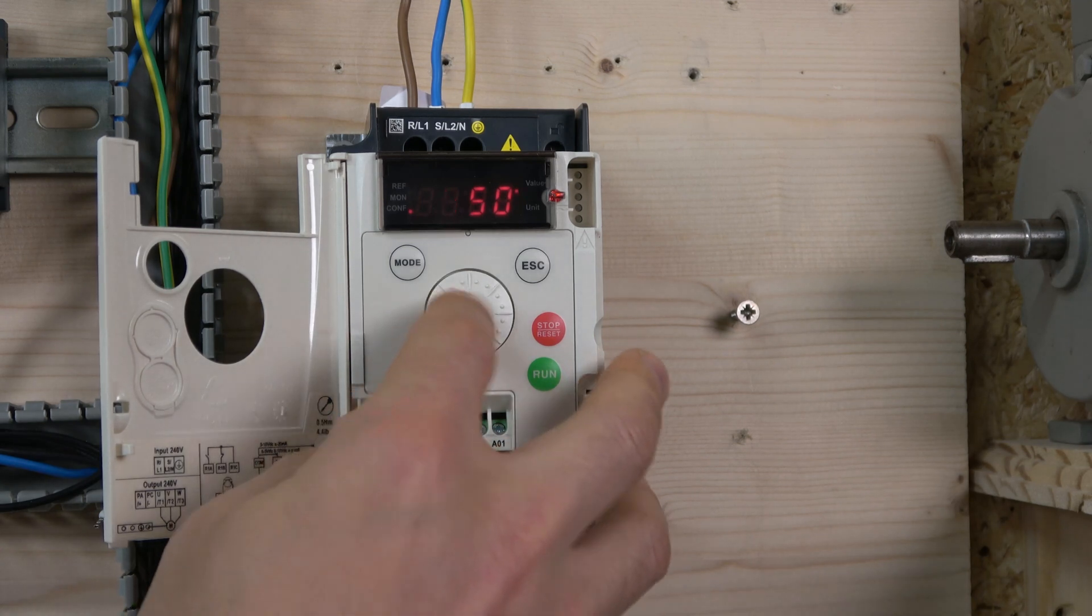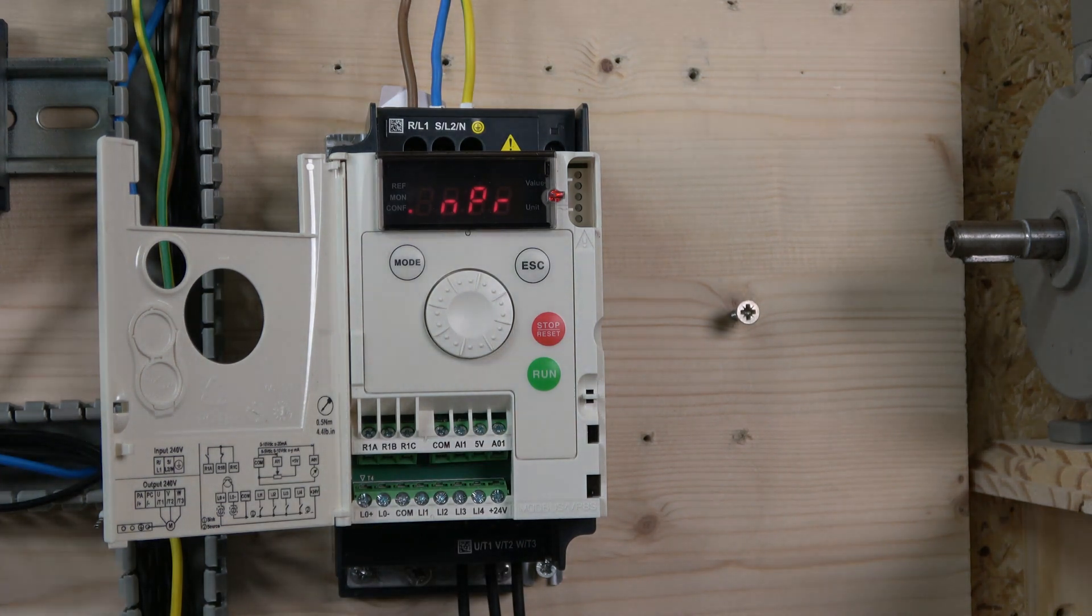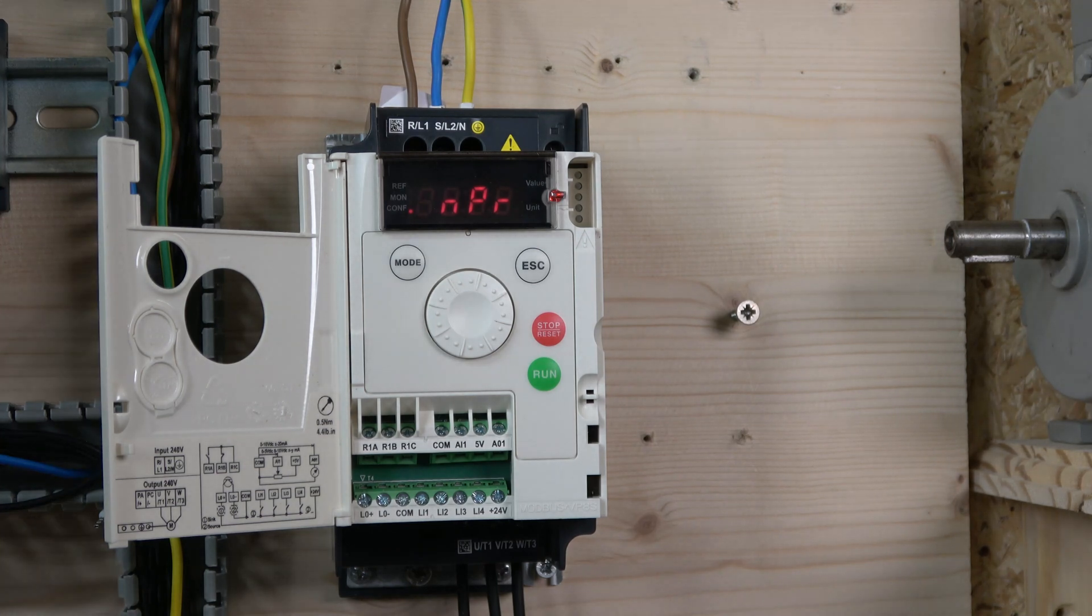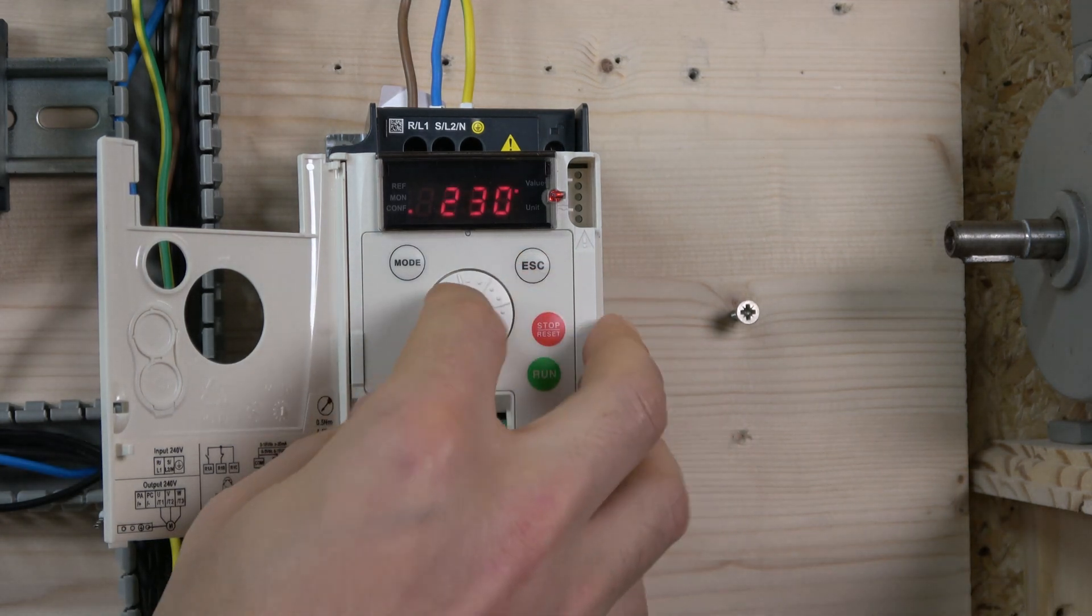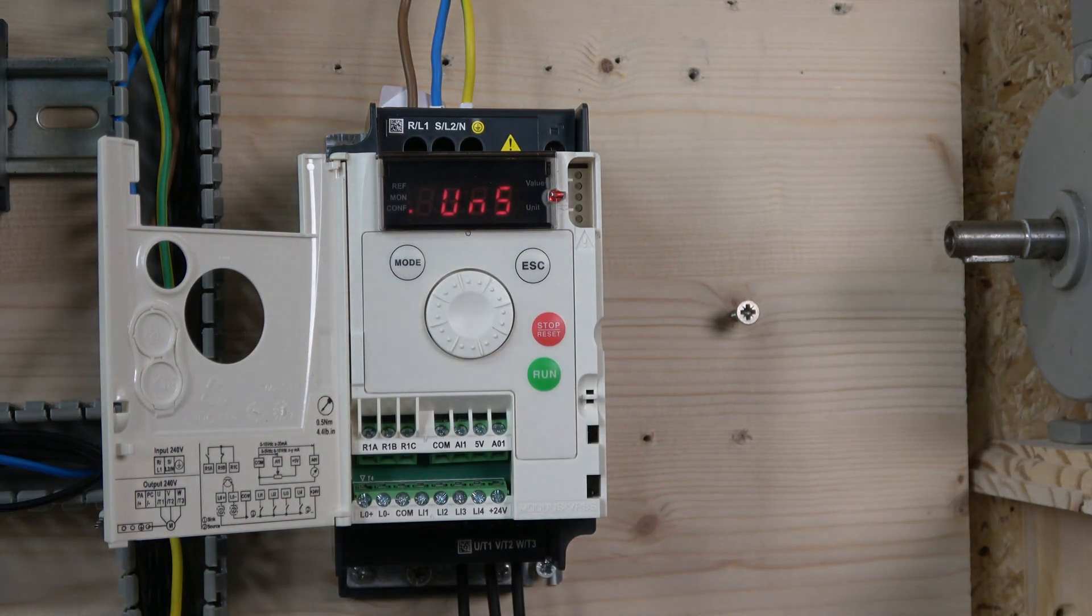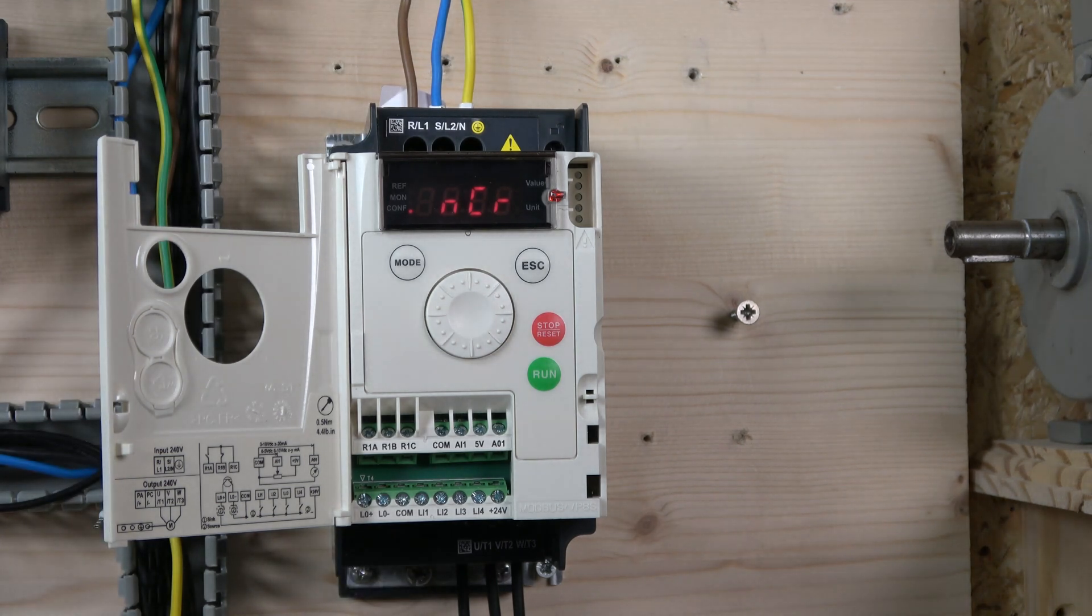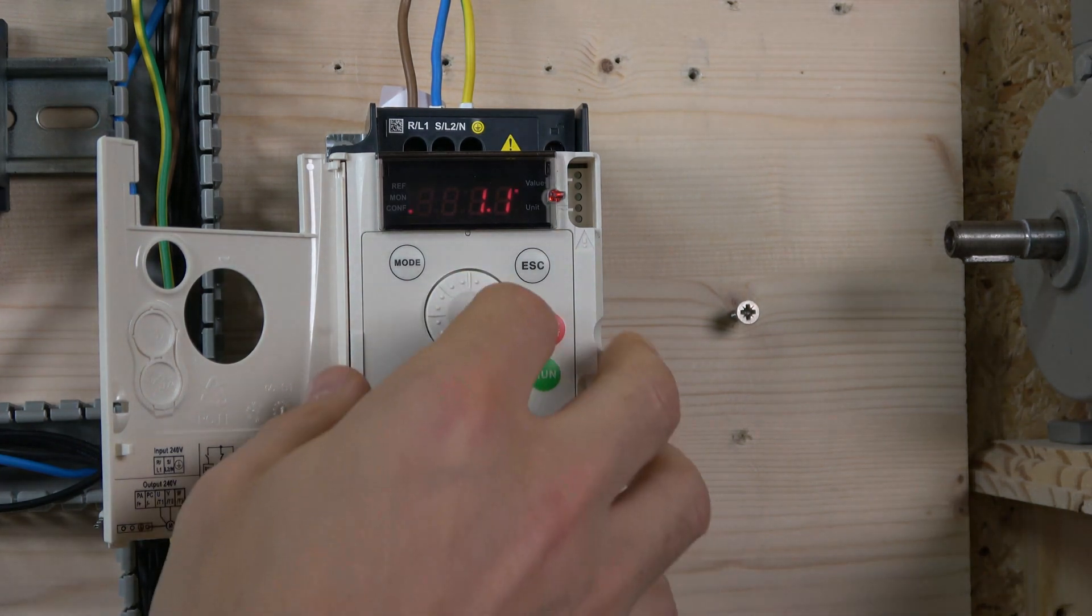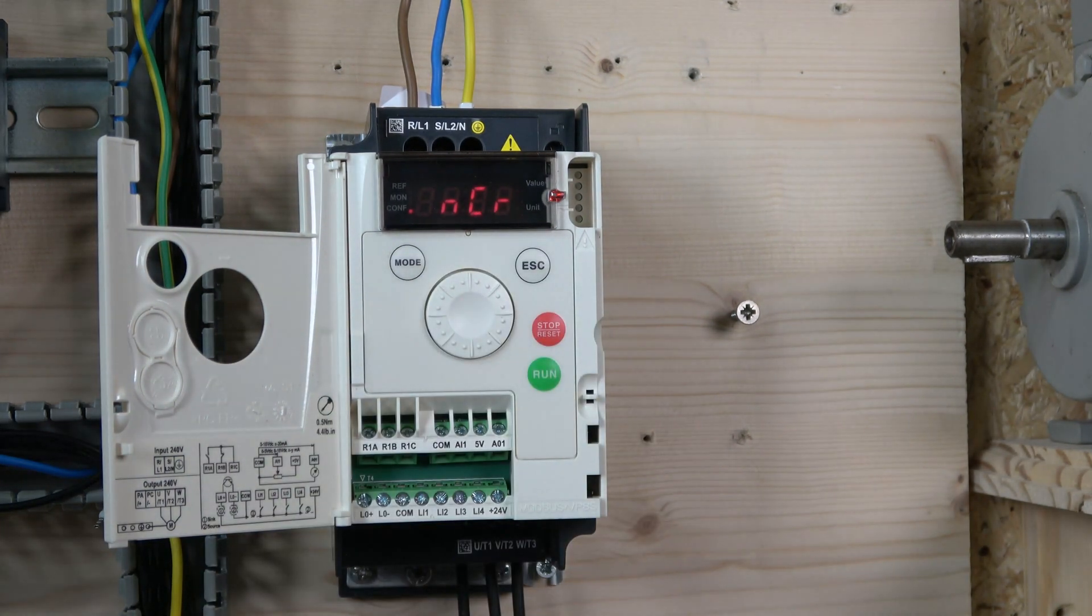Next is nPr, the power rating. Mine has been changed to 0.18 kilowatt, already set since it's a 0.18 kilowatt drive. Next is power factor cosine - not all drives request this. Actually, this drive doesn't have it, so we skip to UNS. Here we check motor rated voltage, which is 230 volts. Next is NCR, motor rated current - exactly what's on the motor data plate. Mine is 1.3 amps. I'll put it at 1.1.